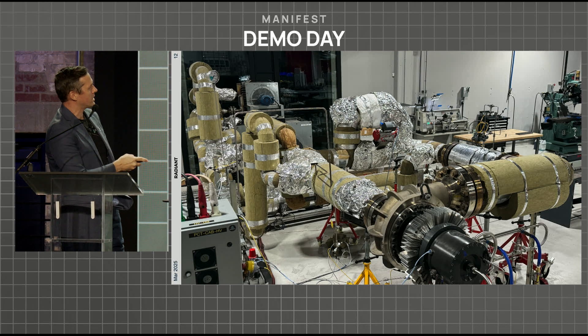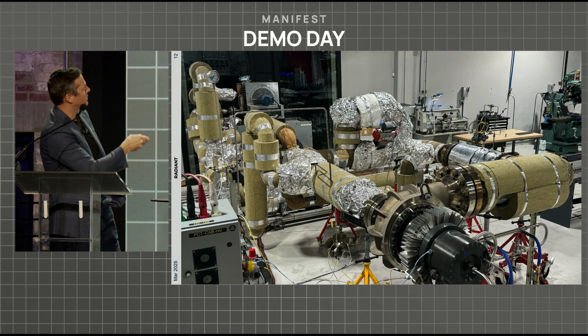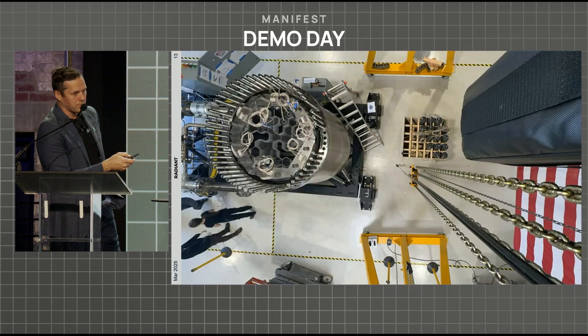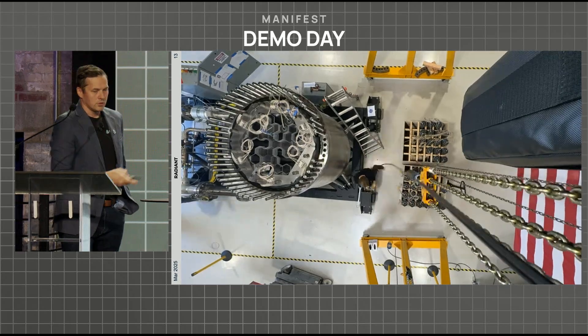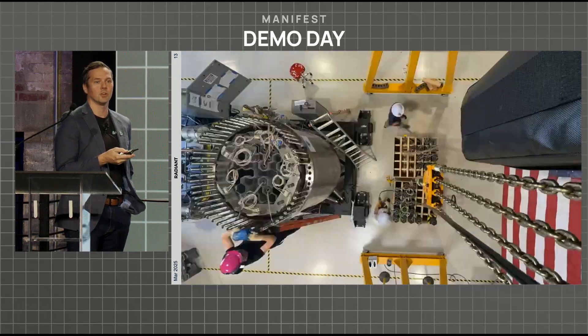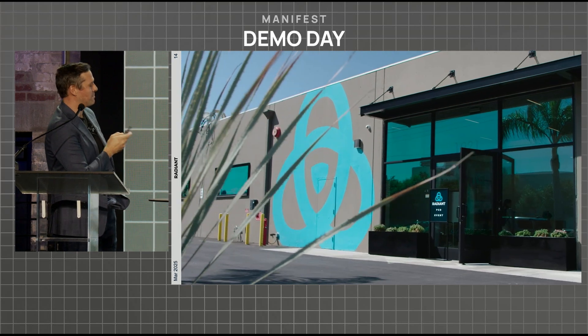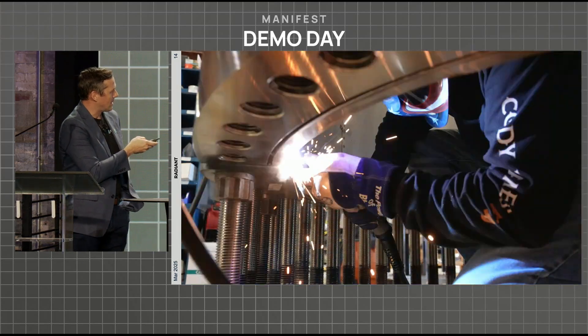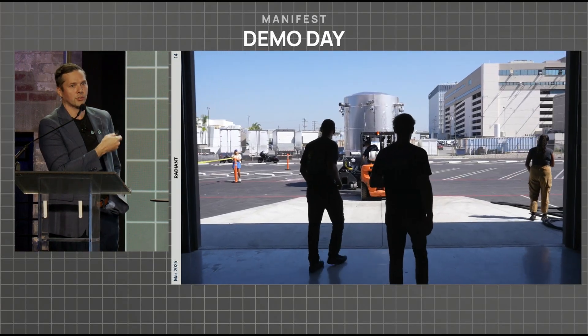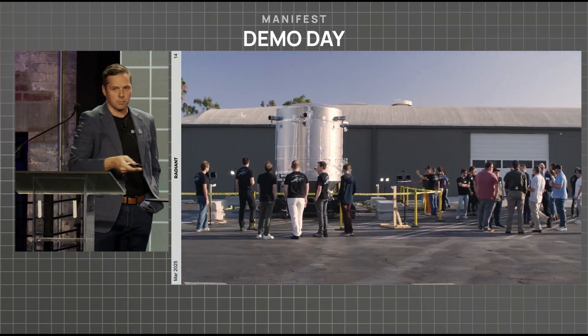This stuff is all real. This is the first iteration of our helium circulator — a 16,000 RPM turbo machine. This is cast Inconel, about 800 pounds of it, bigger than a Falcon 9 turbo pump. This pushes the fluid through the system, and all the other parts here are really simulating the components of the reactor. We also built up a reactor in September and then used electric heat to get it up to its full operating temperature with helium. It really took us only about one month to assemble. The trouble is access to the pieces, and of course this has no nuclear fuel in it. This is showing some of the precision-machined graphite and welding. There are about 260 total channels in that system, and we use this to validate the passive cooling functionality where we don't need a pump even if power goes out.